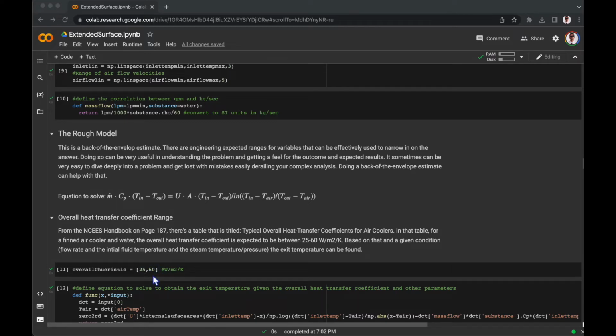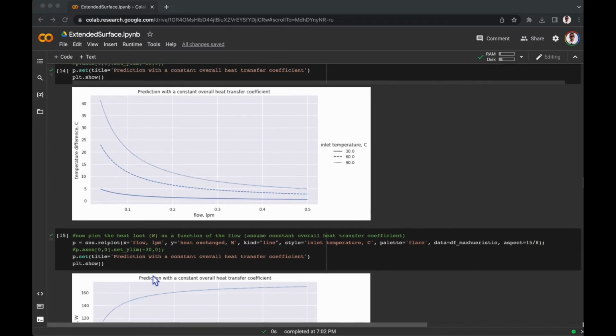We've used just 60, and you can see doing that you get this kind of effect with the flow, as well as for the temperature difference through the heat exchanger as a function of flow for different inlet temperatures. Of course, as you get higher temperatures, you get higher temperature differences as the heat can dissipate, and there's a greater driving force.